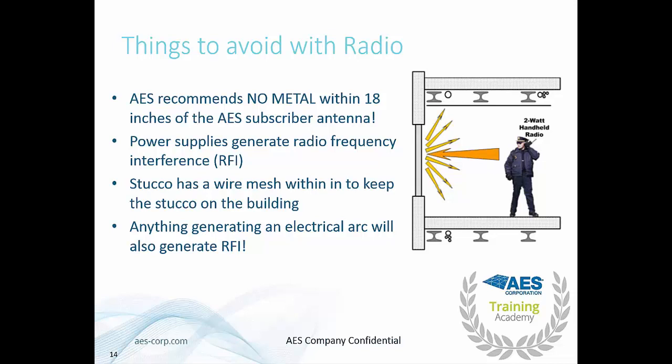There are some other things to consider. Power supplies generate radio frequency interference. Generally, fire alarm manufacturers put the power supply on the left-hand side, so we recommend when mounting the AES subscriber to mount it on the right-hand side. Stucco also has a wire mesh within it to keep the stucco on the building.